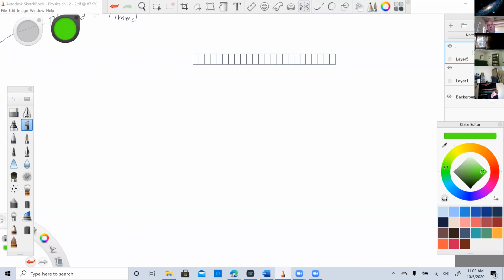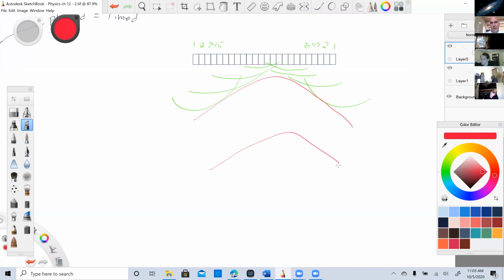All right. So we've already spoken about phasing. I take this entire set of elements and I start 1, 1, 2, 3, 4, 5, 2, 3, 4, 5, and keep going until I get to the middle. I will focus the beam because these start on the outside. And I've essentially just created a wave front that is focused down to that point. So that's phasing and focusing.